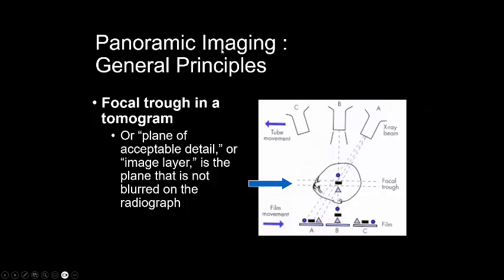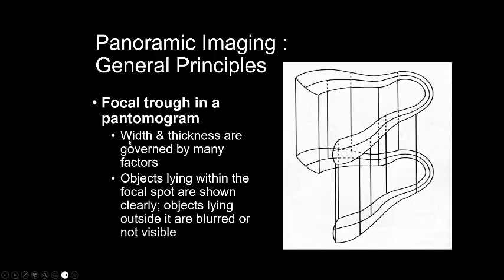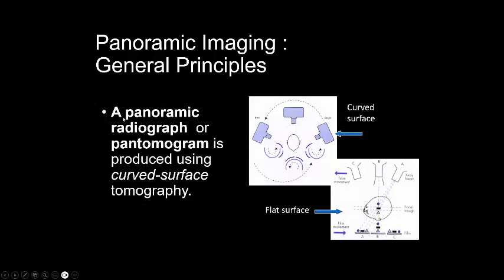The general principles of panoramic imaging: there is a focal trough in the tomogram, which is the plane of acceptable detail — the image layer that is not blurred on the radiograph. The x-ray moves in one direction while the film moves in the opposite direction. Objects within the focal trough are shown clearly; objects lying outside are blurred or not visible. A panoramic radiograph is produced using curved surface tomography.